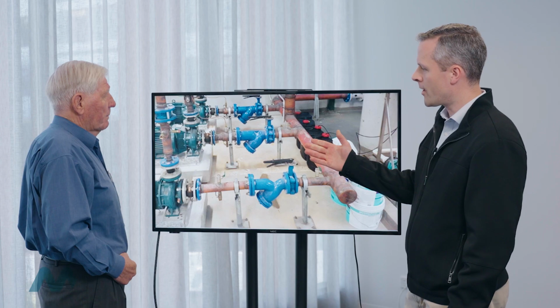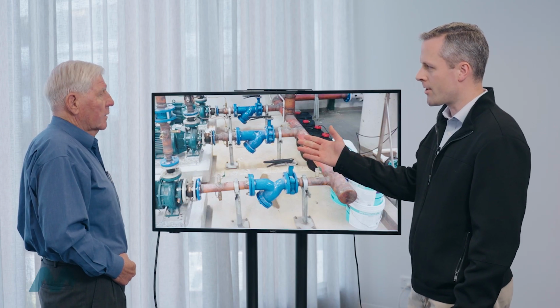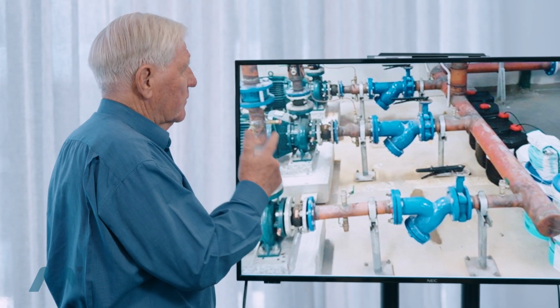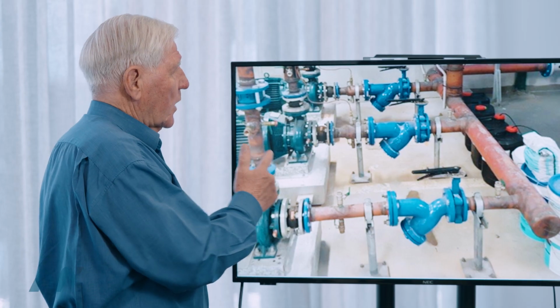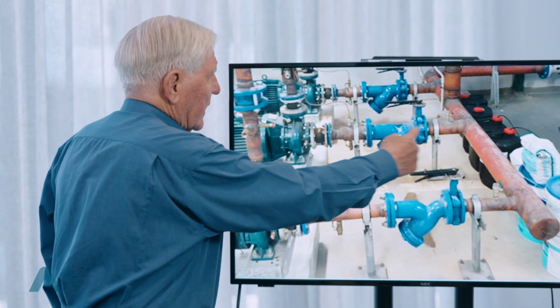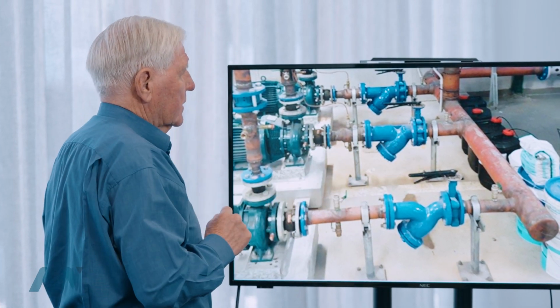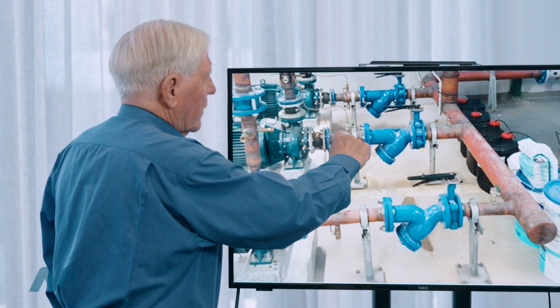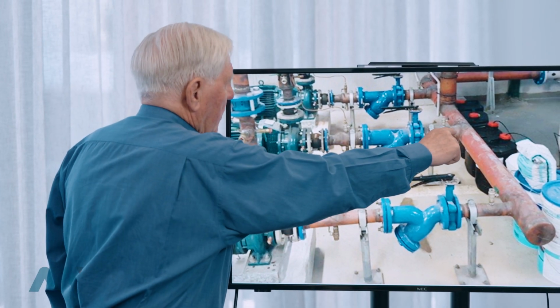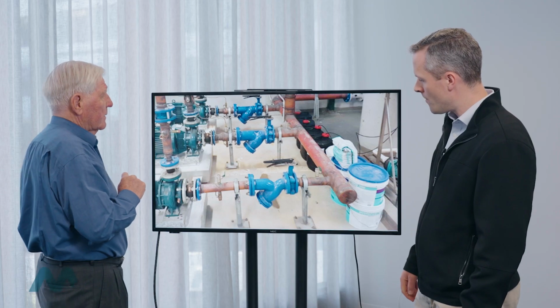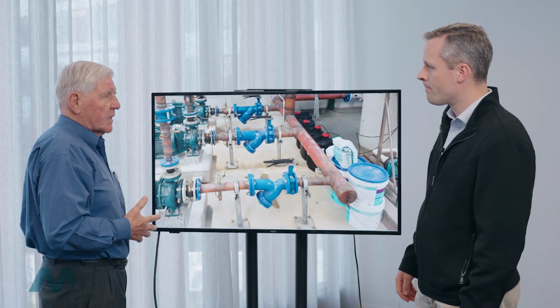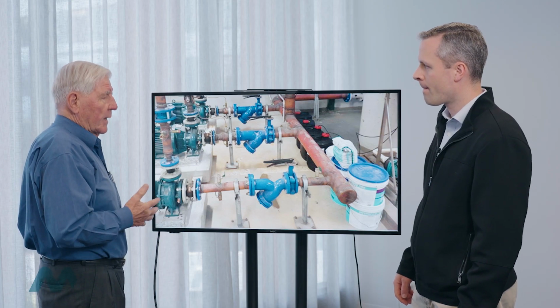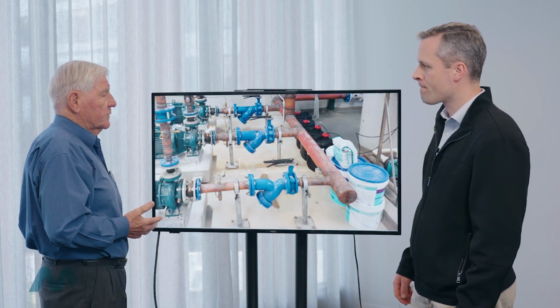So why can't you use concentric reducers on the suction? The general principle for pump suctions is you don't want trapped air in this line. And if you've got a concentric reducer, you've got a potential for trapped air all along there. Sure. And trapped air means pump underperformance and potential for noise.